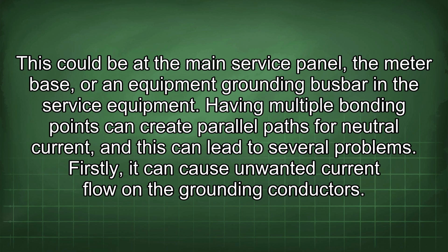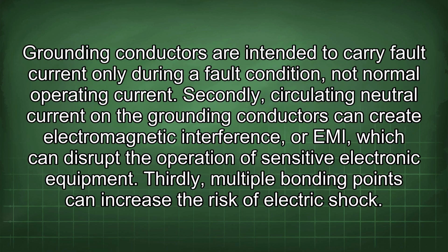Having multiple bonding points can create parallel paths for neutral current, and this can lead to several problems. Firstly, it can cause unwanted current flow on the grounding conductors. Grounding conductors are intended to carry fault current only during a fault condition, not normal operating current.